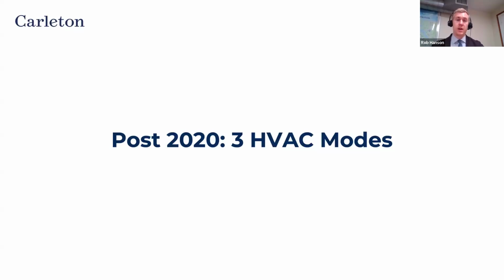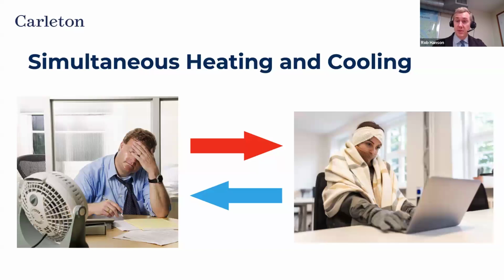The first mode is simultaneous heating and cooling. Using a heat pump, we can move heat around campus. On any given day, some buildings are too cold and need heat, while others are too hot and need cooling. Using our heat pump and distribution system, we take heat out of the hot room to cool it to a comfortable temperature, and give that heat to a cold room to warm it up. That's one of the most efficient ways to heat a building, or in our case, a campus.